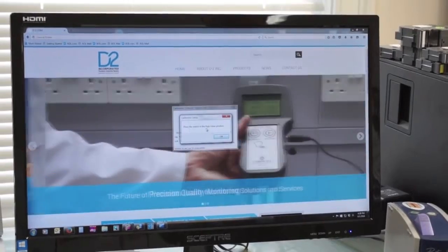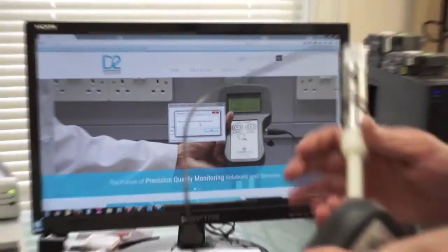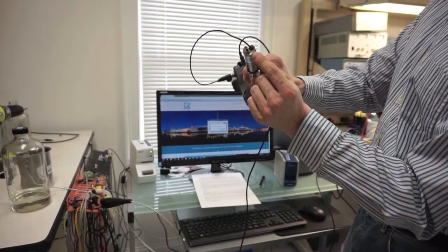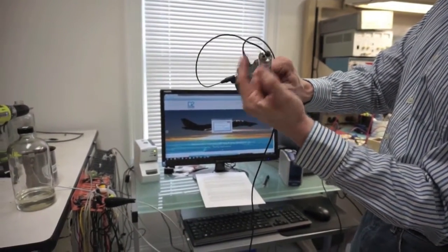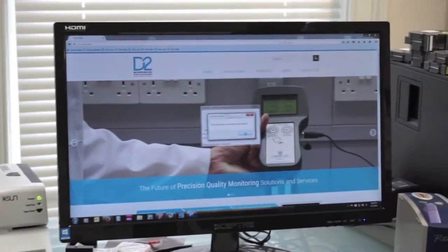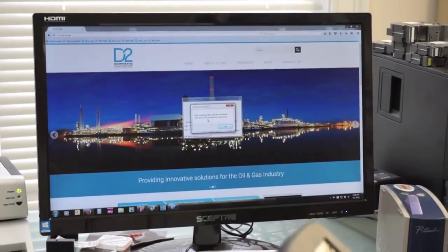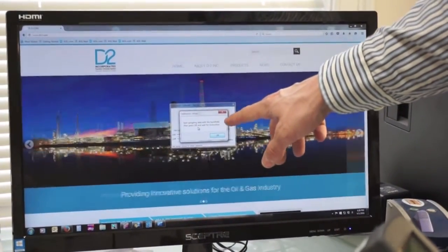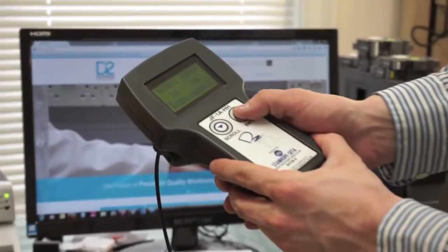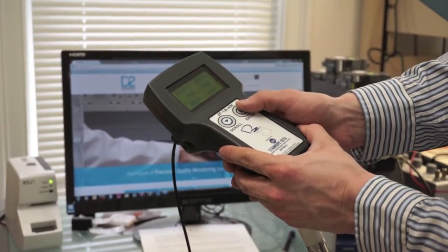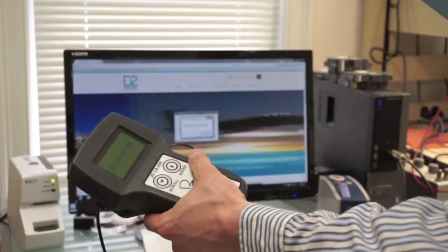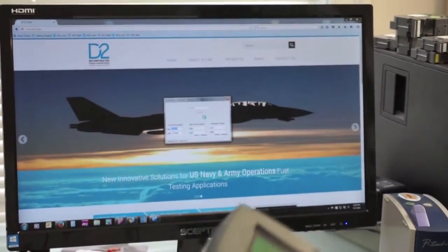Then it says, place the switch into the high value position. So you look at your VF tip, which has an H for high value and L for low value, and you make sure the switch is in the high value position. Then you hit OK on the screen. Then it says, start sampling the data with the handheld, then press OK and wait for notification. So you hit enter to sample on the handheld, enter for location 0. Once you've hit that, it says calculating, so you go back to your computer and hit OK.